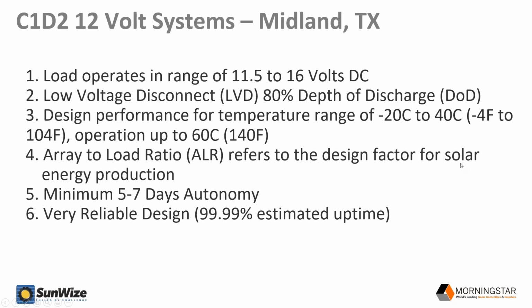Okay, so we're going to start with 12 volt system architecture, and these are our design parameters. The first design parameter is that the load is going to be able to operate off the nominal DC voltage range of the 12 volt battery bank. So basically your equipment needs to be okay to run on a DC voltage range of 11.5 to 16 volts. The second one is that we've set the low voltage disconnect for the batteries at 80% Depth of Discharge.